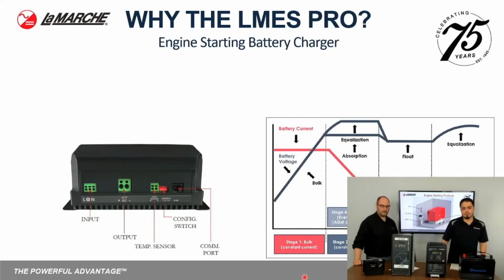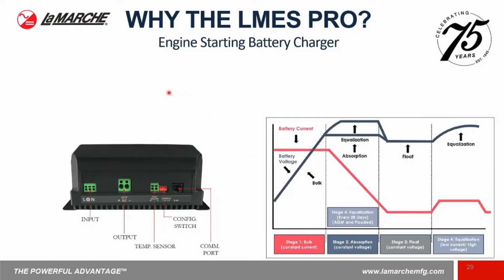As you can see here, we have a nice little image of the front itself. You have some very defined connections as far as your inputs, your outputs, your temperature sensor connections, and these config switches here are what would actually allow you to change your voltage as far as 12, 24 volts, or different voltage ranges for your lead acid, NiCad, and supercap configurations.